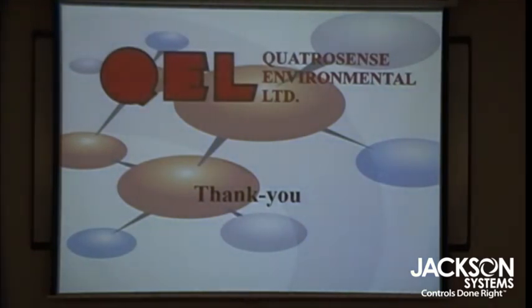So in some instances, or the other thing you can do, if you have a spare sensor, just send the other one back to us and we'll recalibrate it and send it back to you. So you can always have a spare. We do that with some of the municipalities in Canada for swimming pools. So we actually have an exchange program. So every 6 months, we send them out sensors, they replace them, send the old ones back, and then plug it in. So they have a couple of techs that go around to do that. So we have that recalibration program. Cost of the recal is $50. So it's relatively inexpensive.